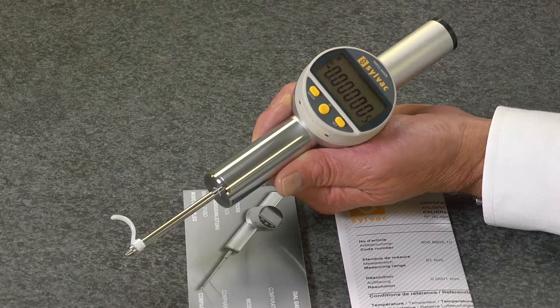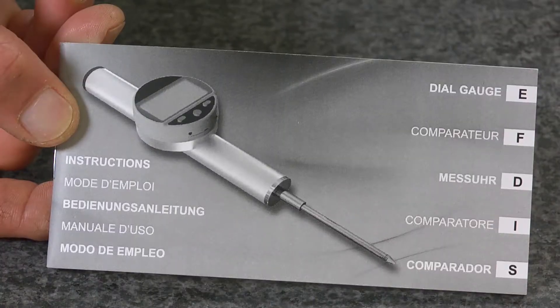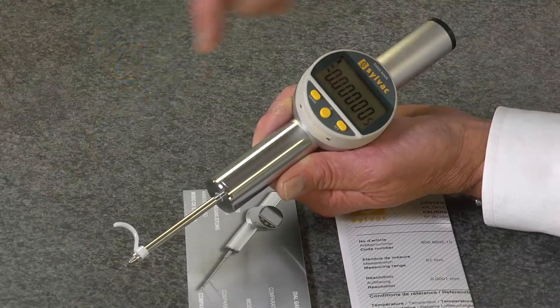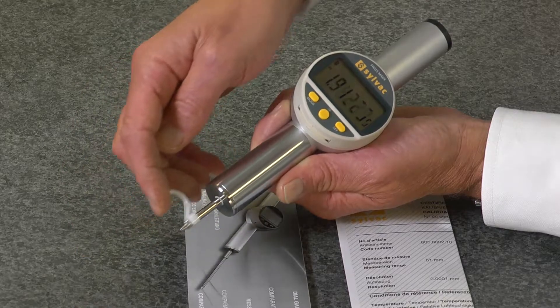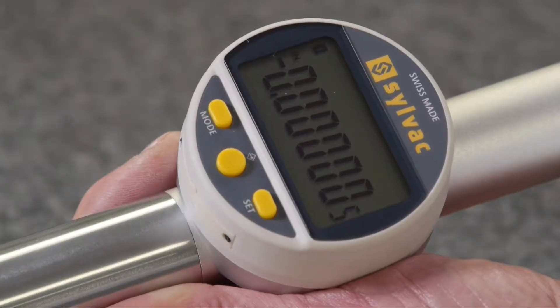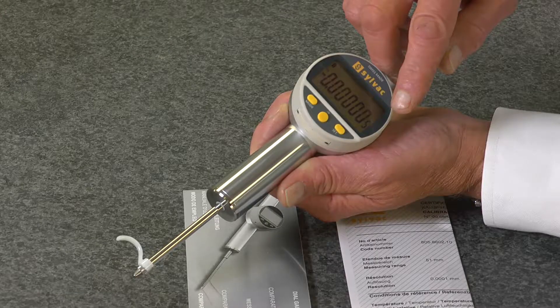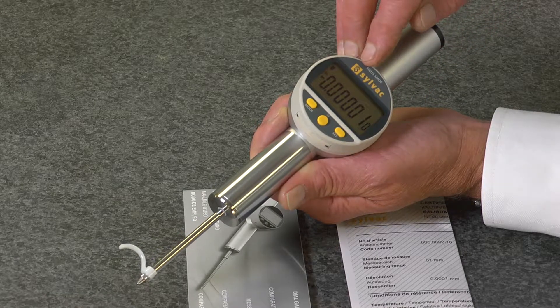The Fowler Sylvac S-Dial Pro High Accuracy Indicator includes an instruction manual and manufacturer's test cert. It has a full two inches of range, a resolution of five millionths of an inch, repeatability of ten millionths of an inch, and an accuracy of sixty millionths of an inch.